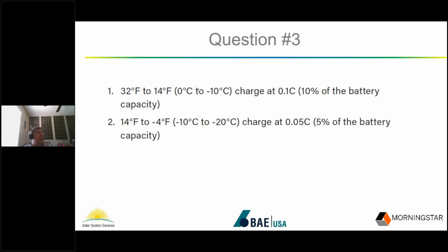And that's at the 10% rate. This is a 0.05 C, or 5% of battery capacity rate, which is even worse. That's below 14 Fahrenheit. So again, look at the notes, read the manual, look at the fine print, because this stuff wasn't obvious.